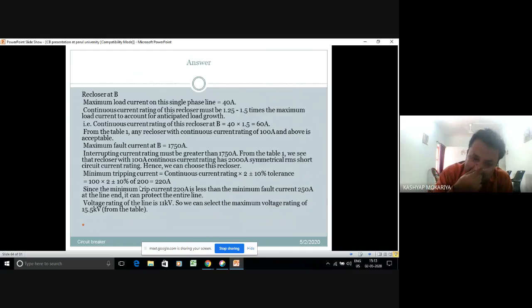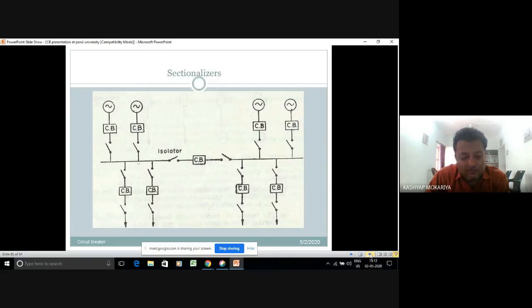So why did I cover this? Because when a diploma holder, ME or any candidate enters into an industry, these things are very precious to them. Many people know the basic operations of a breaker, but symmetrical fault analysis, unsymmetrical fault analysis, then the 3 states of breaker, calculating the breaker rating in MVA from the different states, and calculation on design of the reclosers, this is very important.